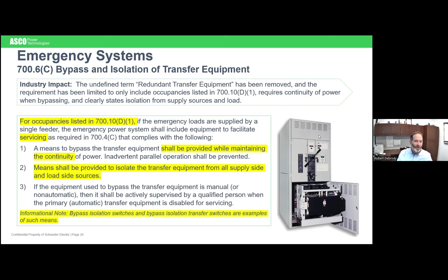So as you see up above, they say means shall be permitted to bypass and isolate the transfer switch equipment. That was encompassed everywhere. You can always use a bypass switch. And then they added that redundant transfer switch equipment paragraph. So they got rid of both of those, and they said, okay, let's put it all in a more concise way down here and describe it a little bit differently. So they say for occupancies listed here. So I'll jump back and show you what it's actually down further. We'll talk about what specific occupancies they're talking about here. So that's where they're putting their exception. Up above in 2023, you see these are the four exceptions they gave for when you don't necessarily have to have that redundant or bypass isolation transfer switch.